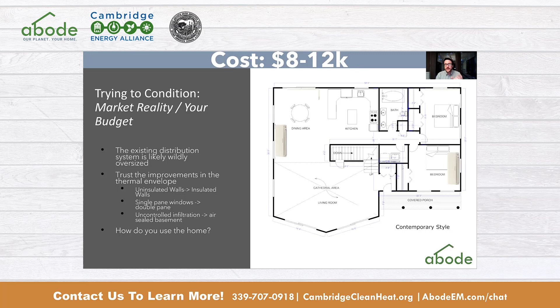If you're just putting in 2 units and there's not catastrophic air leaks and heat isn't just freely flowing through your walls, the heat from the heat pump, whether or not it's located right in that room, has enough time to migrate into the space before it's lost to the exterior. Personally, for my home, I had a very noisy steam radiator in the master bedroom that was turned off all winter, and in my daughter's bedroom, electric heat that we never turned on. My house is well weatherized, but we didn't notice any temperature difference, so we're comfortable with our mini split design not including a unit in her bedroom or my son's, but we are getting one. Keeping costs down, keeping performance up, this is something to be aware of. You don't have to do it, but know that it's a real option worth pursuing.